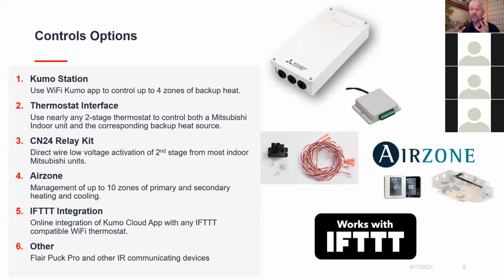If you've got a client who says, I love my Nest, I've got to use a Nest thermostat or Ecobee, okay, great. It's a two-stage thermostat. You'll be able to manage the whole thing. They'll be able to continue to use what they're used to adjusting, and it'll give them the performance out of the heat pump first, and then use the backup system later, and you can adjust the settings within those thermostats.